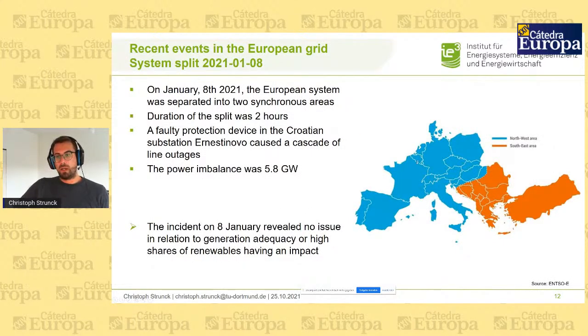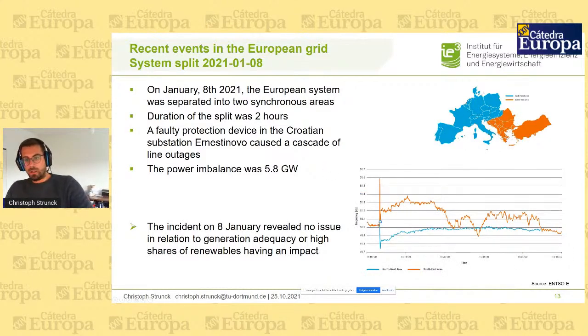The first one in January - you can see here the split line. It started in Croatia and was caused by a faulty protection device, which led to a cascading event that split the system into two islands, with a power imbalance of 5.8 gigawatts. This was very visible in the frequency: the blue island went into an under-frequency state, with frequency dropping to 49.75 hertz, which is pretty critical, but it could be stabilized very fast.